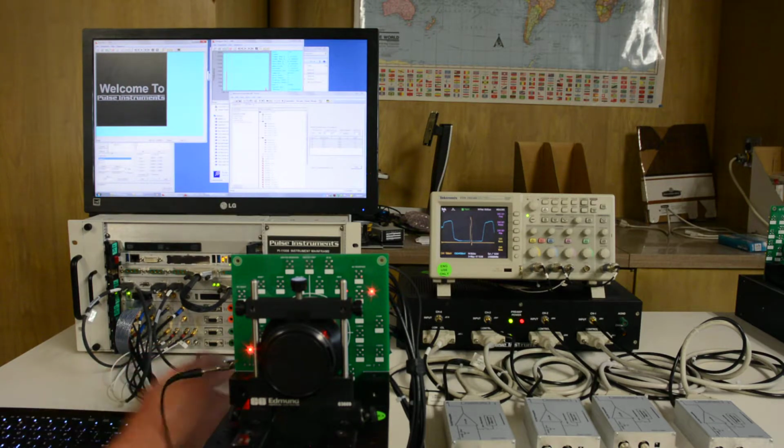Let's attach a real focal plane. So I'm going to load a test plan to run the Ulis microbolometer part. I'm going to load this pip file to set up the microbolometer part, and you can see here that I have various test plans that I can select on the left, and the contents of those test plans are displayed here. I'm going to choose the setup test.